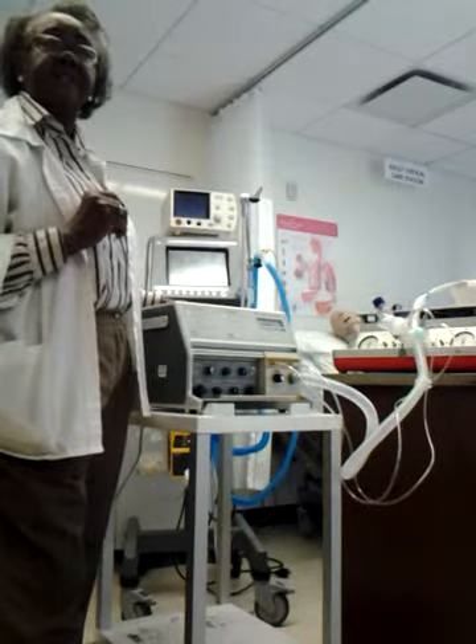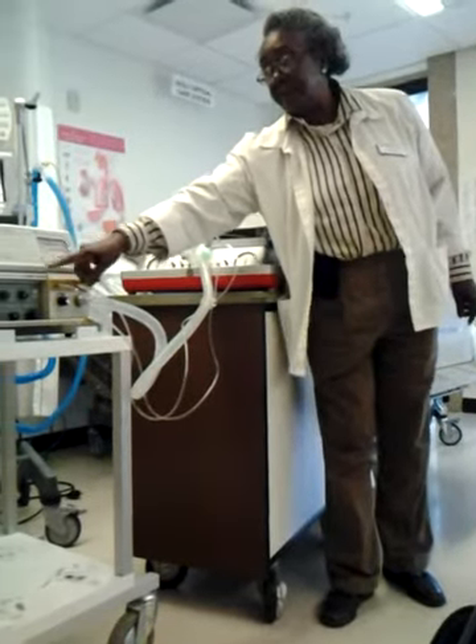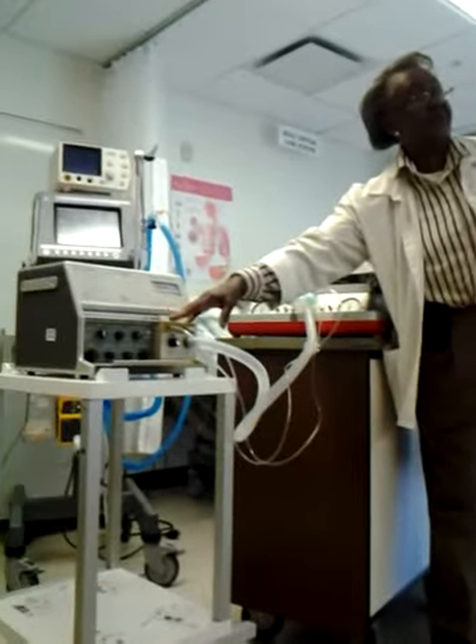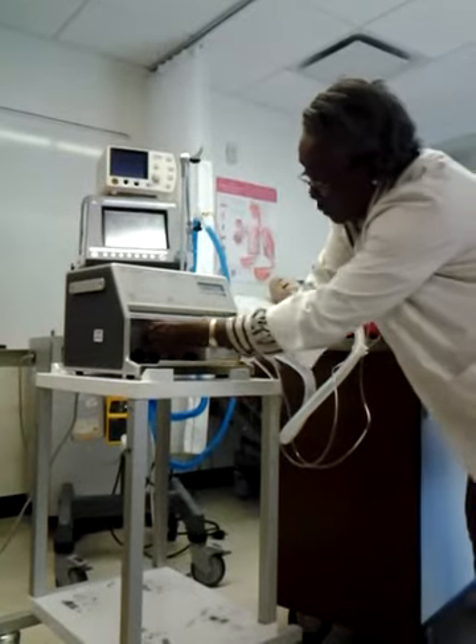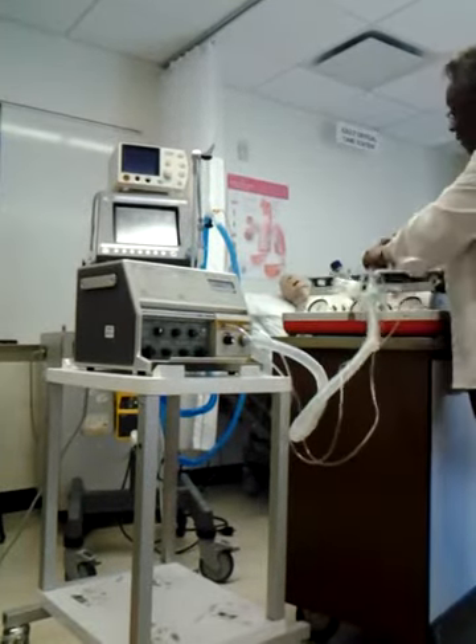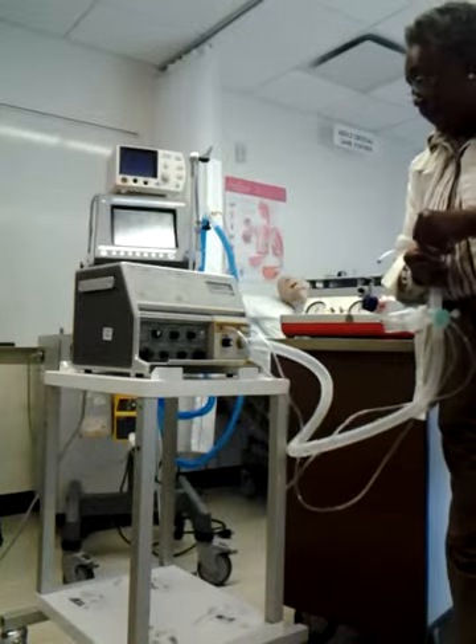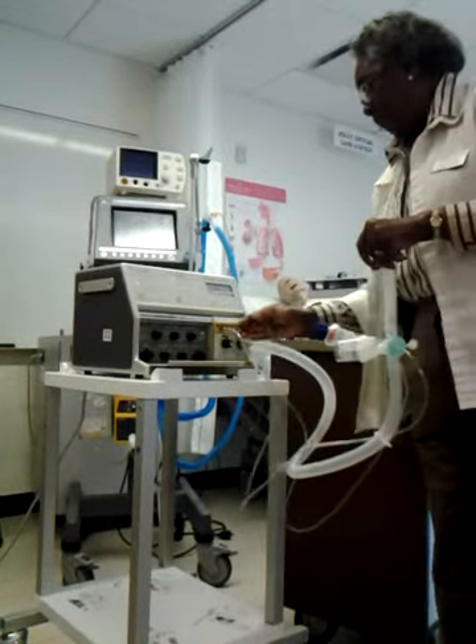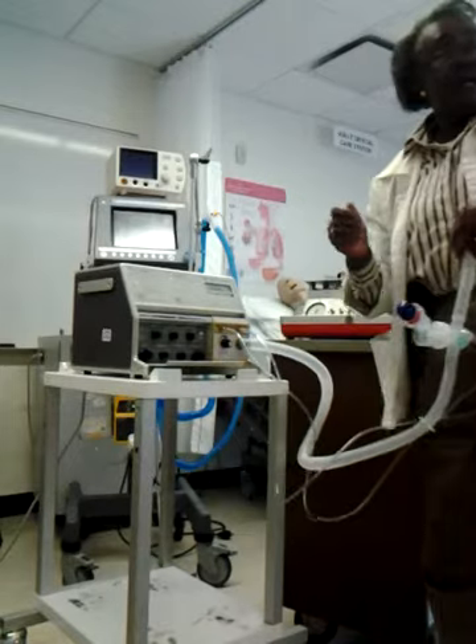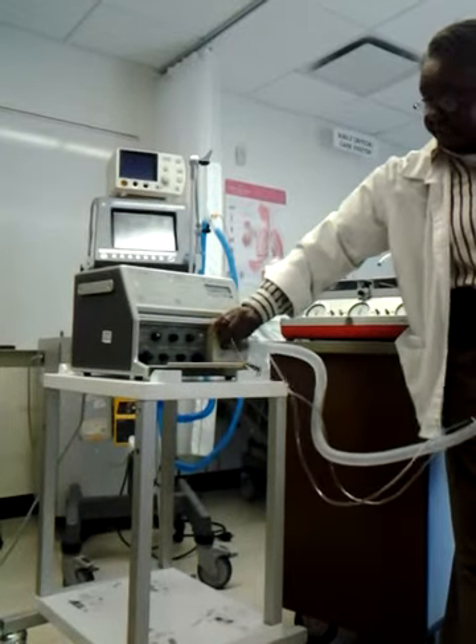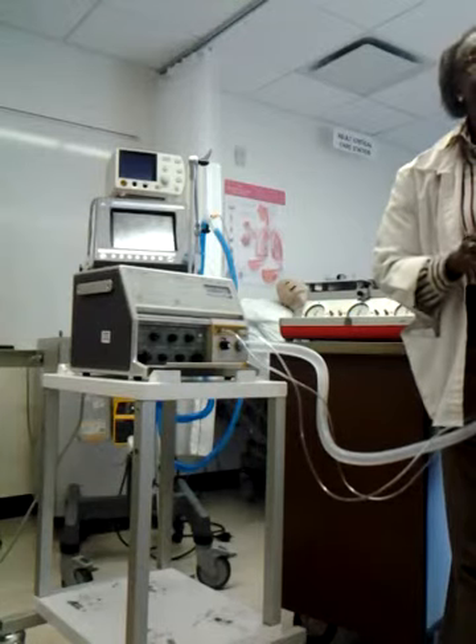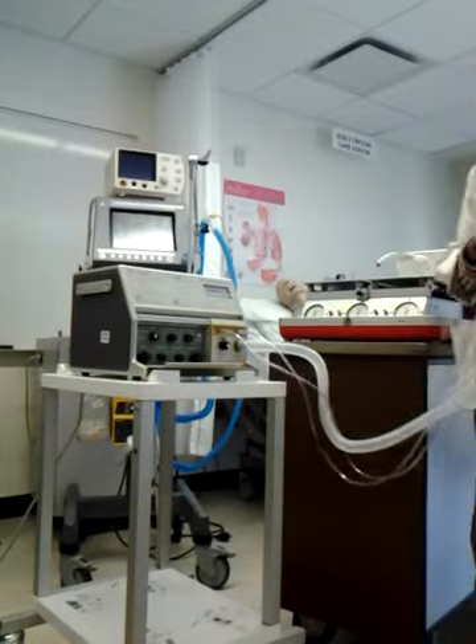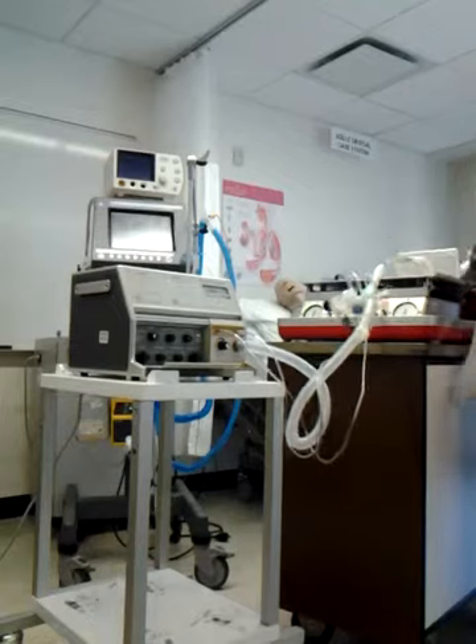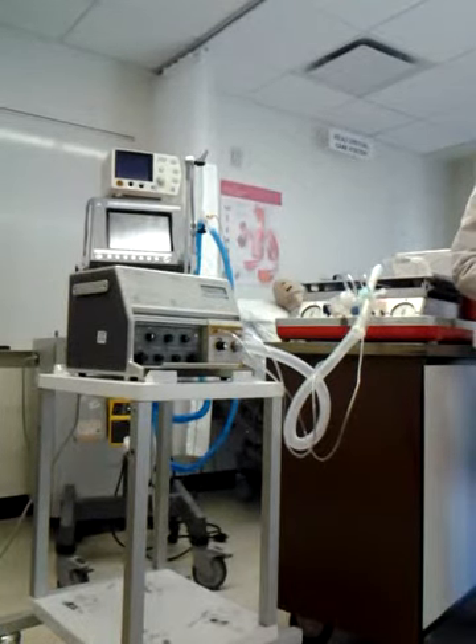Now, you can do pressure control with these devices. The pressure control has to be set using this knob over here where it says pressure. In other words, with volume control, as long as you're setting all of those parameters there, you're in volume control. If you want to go up to pressure control, then you need to get an occluded pressure by occluding it and giving a breath, and this is one of those push-in knobs where it doesn't just turn on its own. You gotta push it in and turn it, and that will set your pressure if you're gonna use pressure ventilation. Very rarely on an adult patient are you gonna see pressure ventilation in the home.